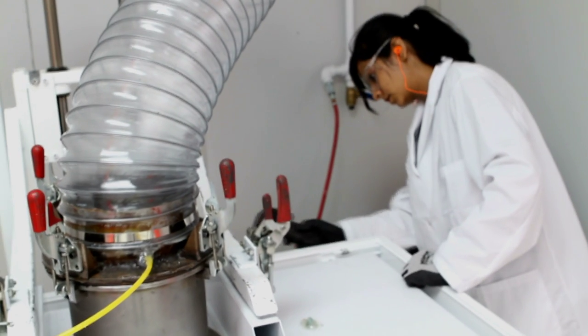Out of that list, the DOP testing is by far the most important. And what that process involves is we take a unit and we verify that the integrity of the casing is 100%. No product is actually going to leave the clean room until it has passed this test and we've recorded that it's passed.